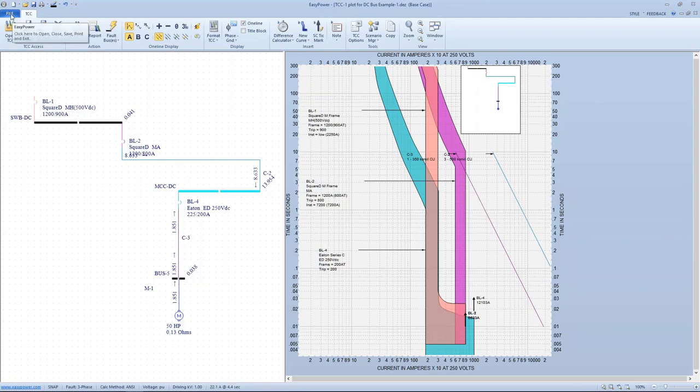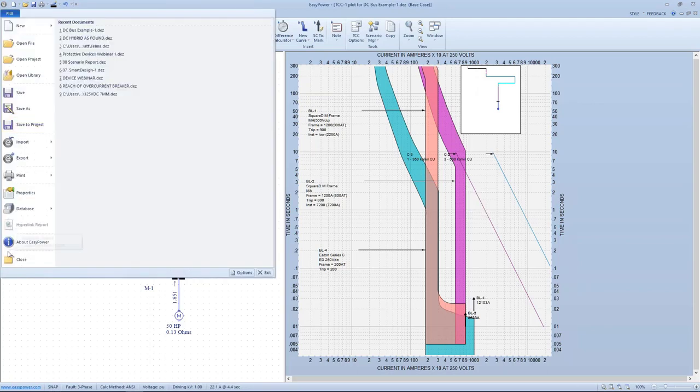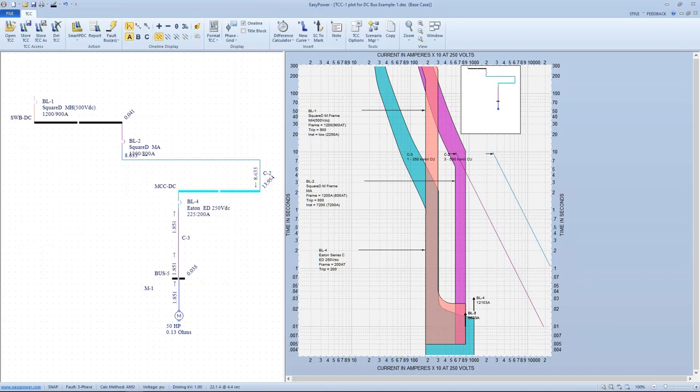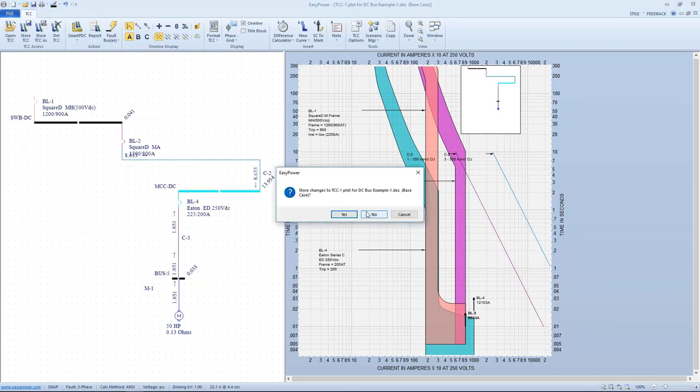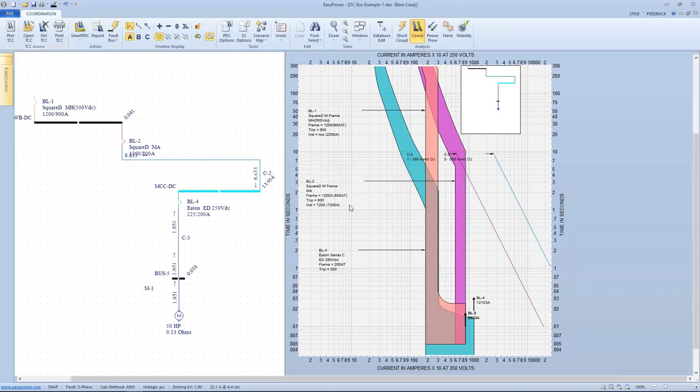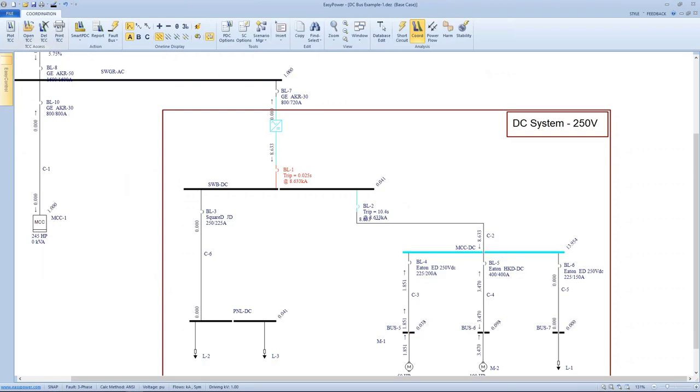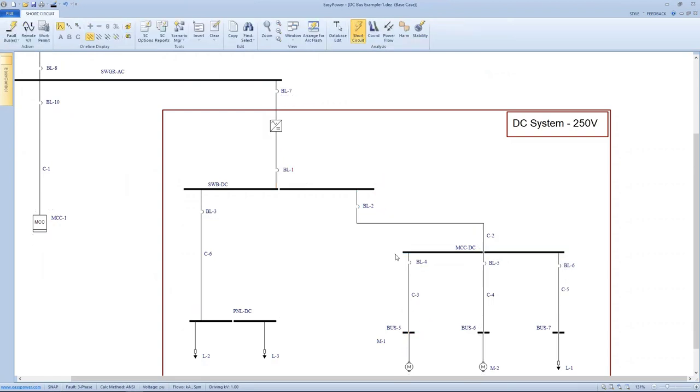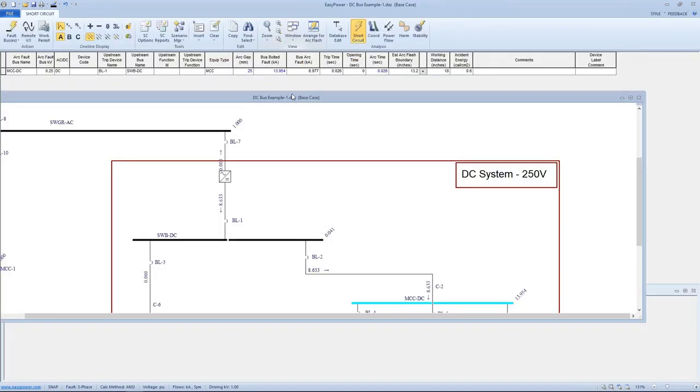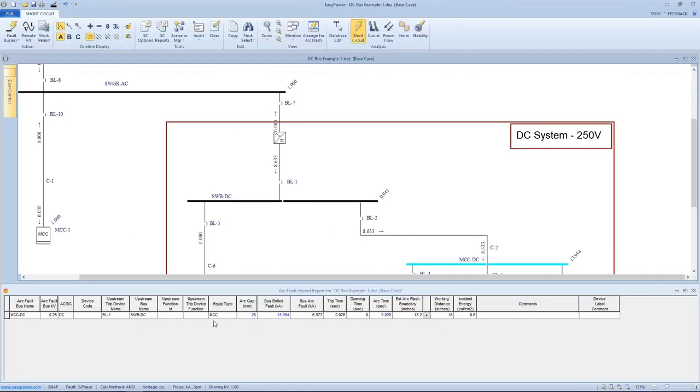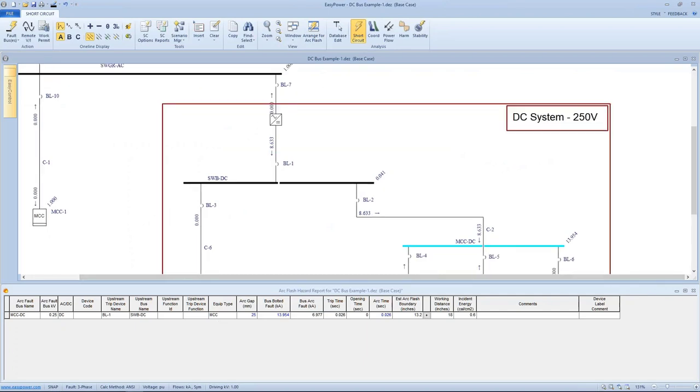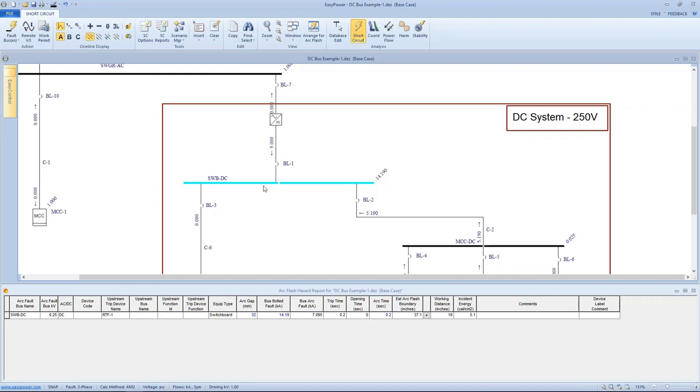So just out of curiosity, let's go back and see, we're still trying to trace down the lack of coordination. Just out of curiosity, let's go back and see what, if we were to fault this bus in short circuit, what's the device that's going to be protecting our system. And what we see if the MCC DC bus faults, the upstream tripping device will be BL1. If BL1 trips, the upstream tripping device turns out to be the rectifier. And so, again, if we want BL1 to be in the system, we're just going to have to live with some miscoordination between BL1 and BL2.